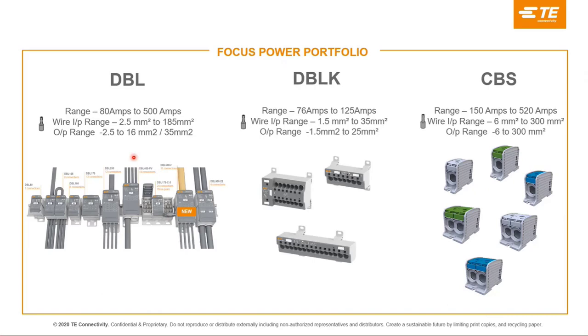Now let's understand the benefits we offer to the customer. First, a 50% reduction in space with respect to the conventional bus bar. Second, up to 70% reduction in time in installation of the DBL inside the panel. Third, and most significant, it is the safest connection system inside the panel, thanks to its IP20 rating, fully protected and covered body design, and a screw design that won't allow the conductor to be damaged by repeated screwing and unscrewing. This improves the overall life of the cable and of the connection in the panel.